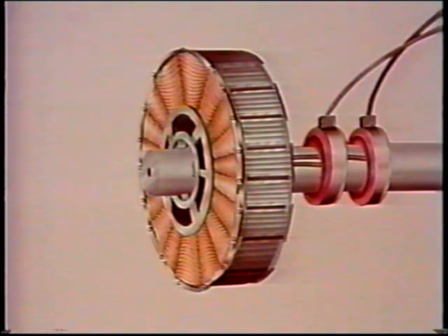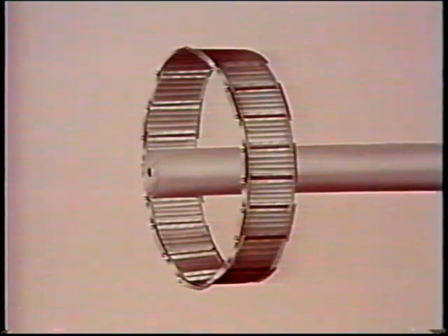A more common method, however, is to have conducting bars called amortisseur bars on the rotor. Amortisseur bars operate on the principle of induction and allow a synchronous motor to operate as an induction motor until the rotor reaches a speed where it can lock in with the stator's rotating field. When amortisseur bars are used on a rotor, they are positioned so that they are parallel to the shaft of the motor. Amortisseur bars are shorted at each end to allow a complete circuit for current flow.